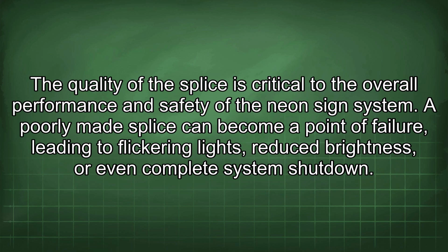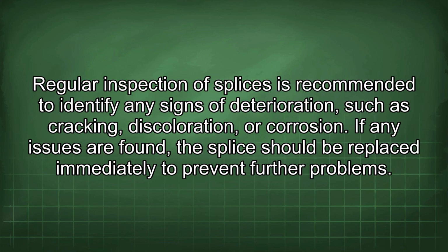The quality of the splice is critical to the overall performance and safety of the neon sign system. A poorly made splice can become a point of failure, leading to flickering lights, reduced brightness, or even complete system shutdown. Regular inspection of splices is recommended to identify any signs of deterioration such as cracking, discoloration, or corrosion. If any issues are found, the splice should be replaced immediately to prevent further problems.